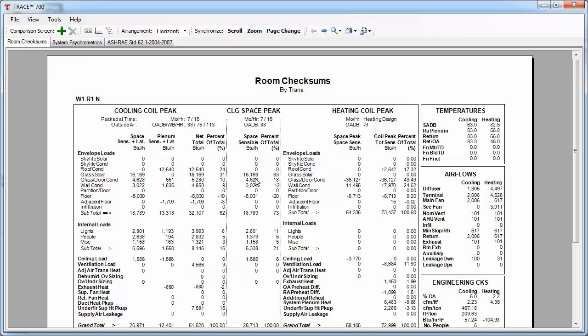So, as an example, let's take a look at the lighting, which is purely sensible load. In this case, it's outputting 2800 BTUH, but in fact, we've inputted 1.3 watts per square foot. We have a 900 square foot space, which turns out to be roughly 4000 BTUH. So, you can see that there's only a portion of the lighting load going into the space, which means that the supply CFM is going to be calculated based only on this space-occupied load.